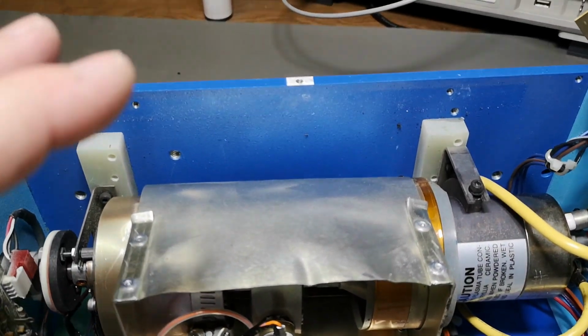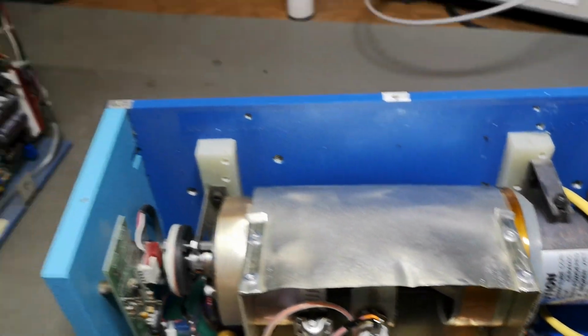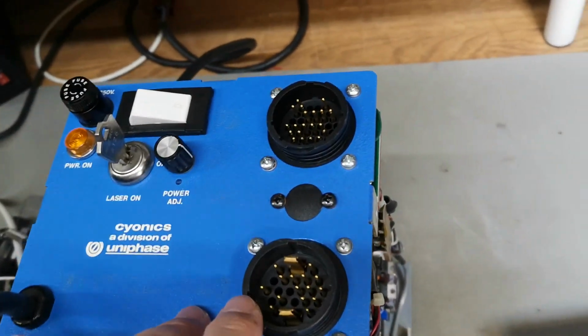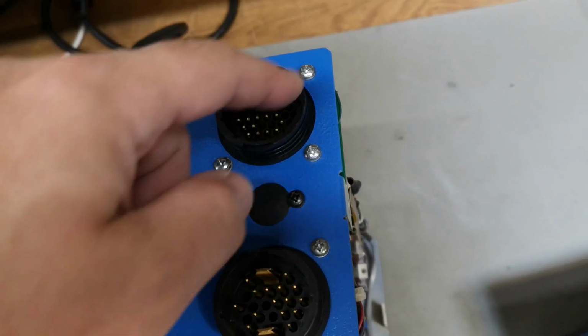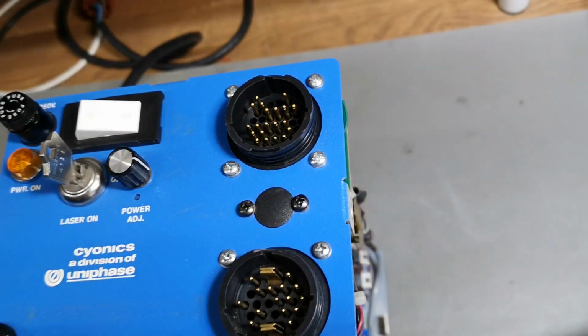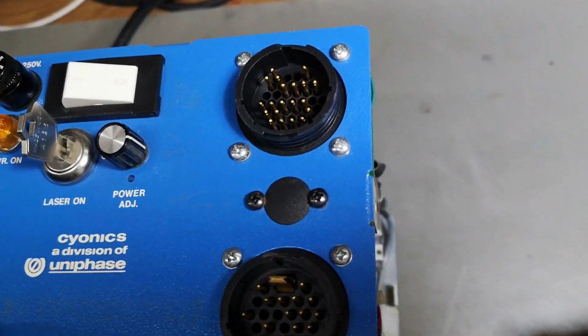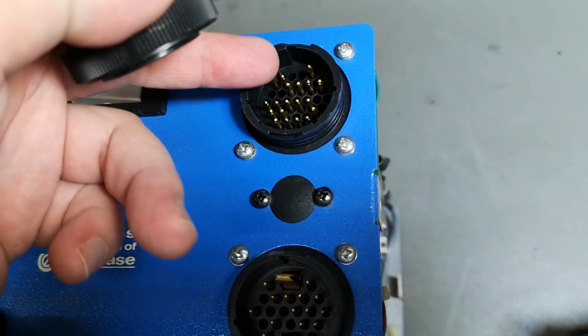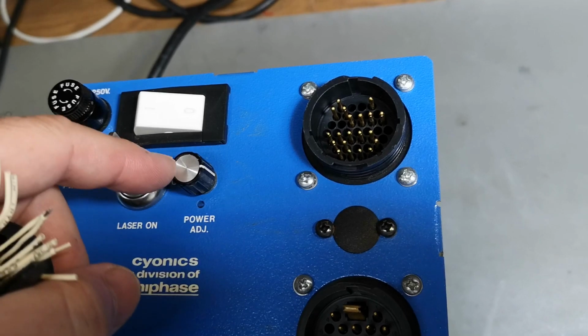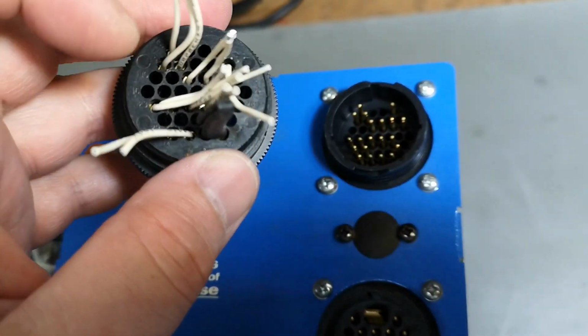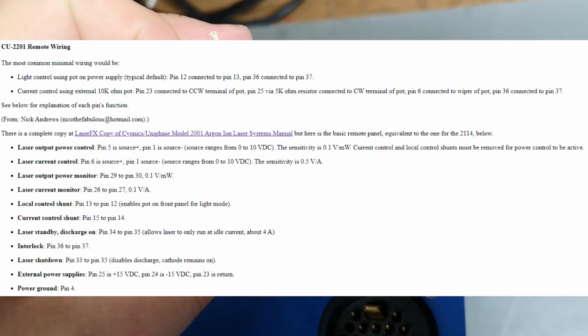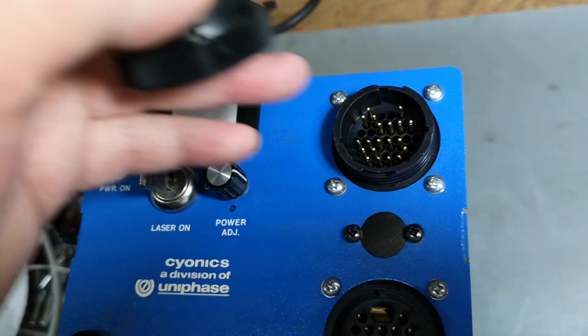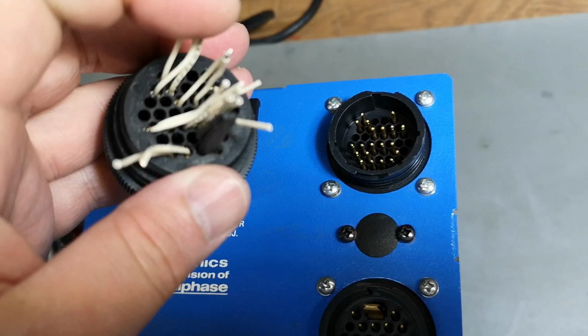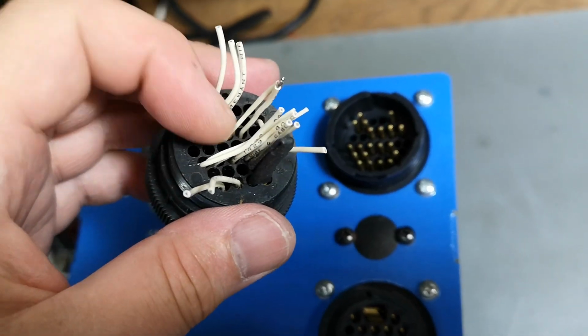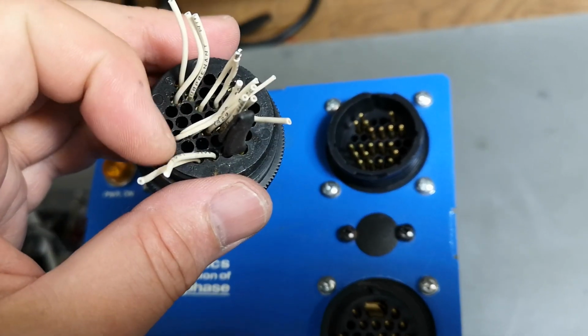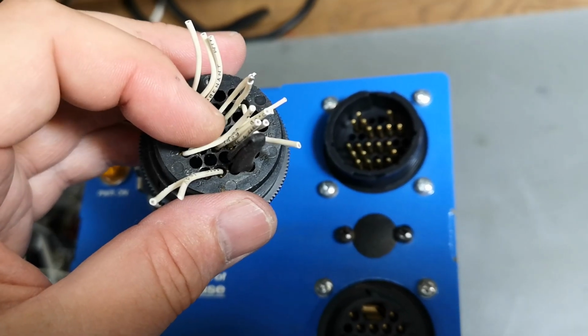I was also able to find a little bit of manual and information online. So what I found so far for the power supply - I found pinouts for the remote control connector. That connector has inhibits and enable of the internal power adjustment potentiometer. What you need to do is short circuit or connect pin 12 and pin 13, which should enable this power adjuster. That was not done because we had no pins in those 2 holes, so I had to remove some other pins that weren't being used and move them to 12 and 13.